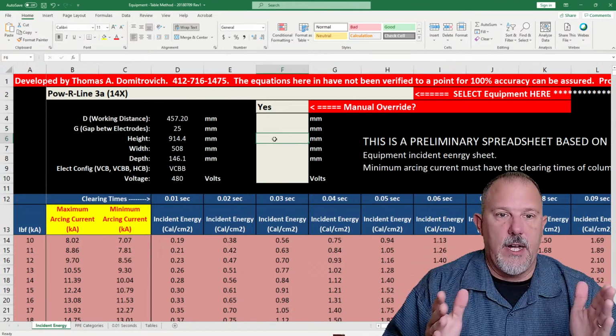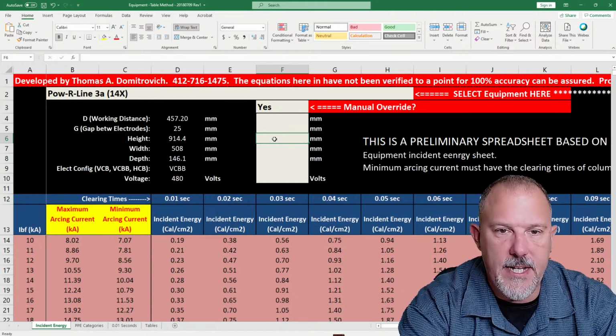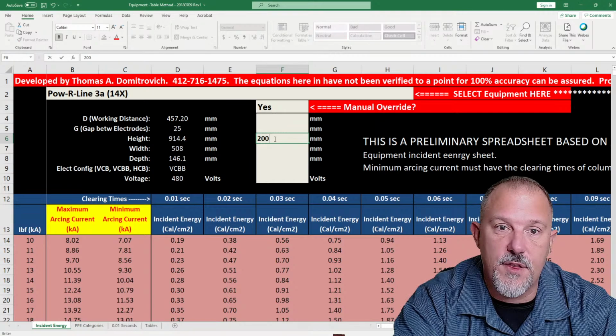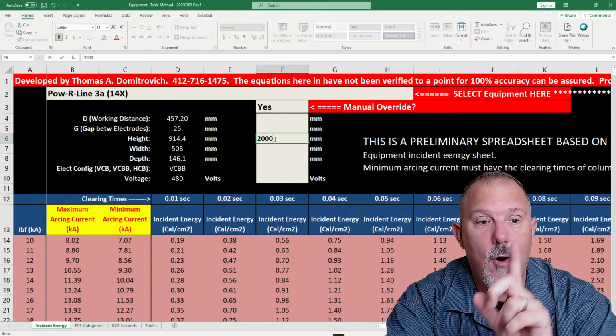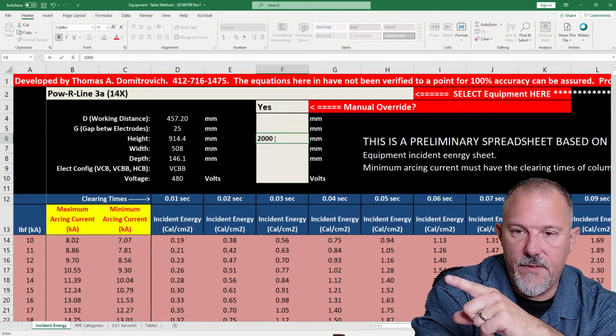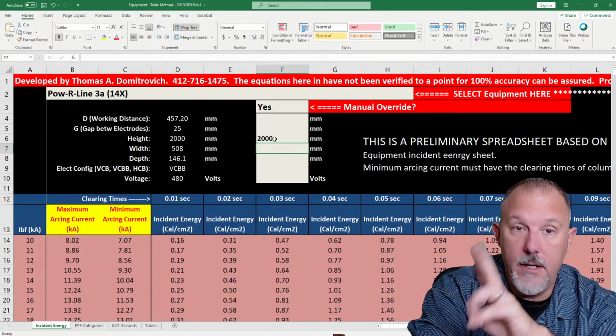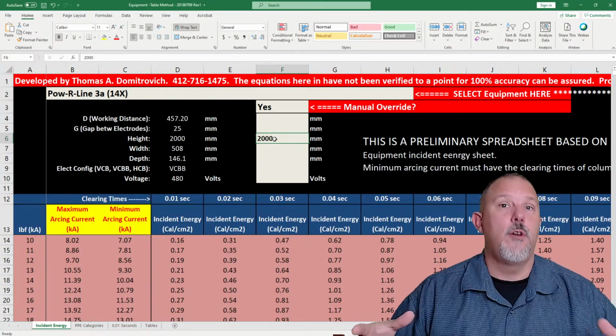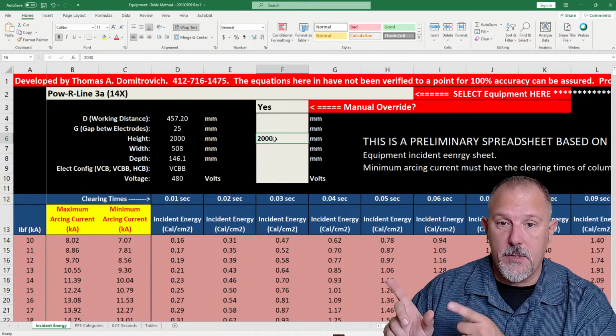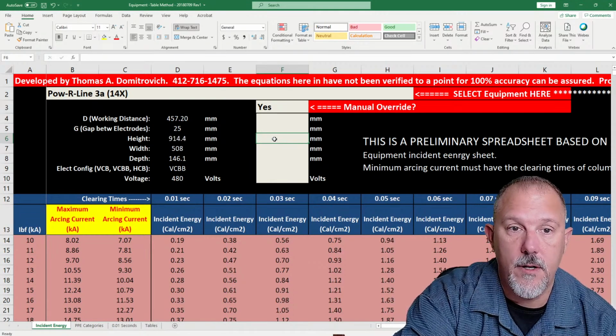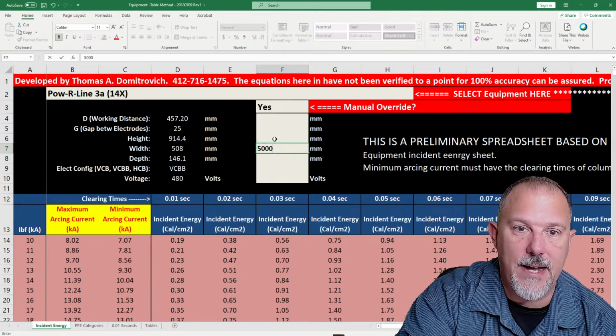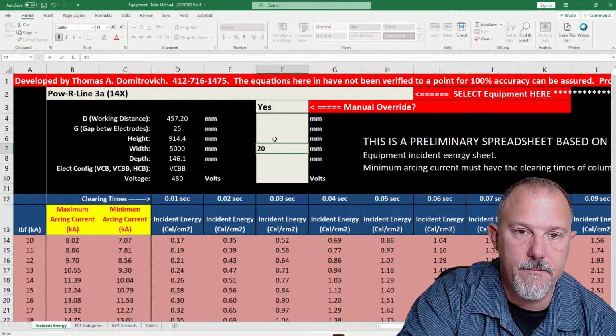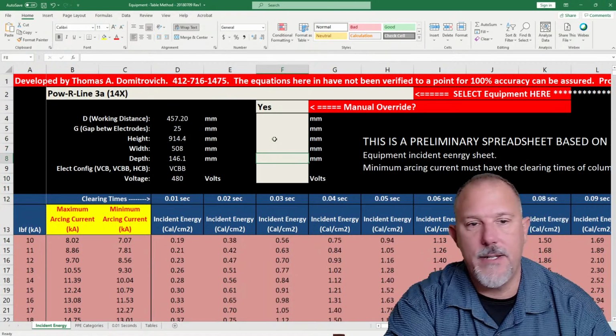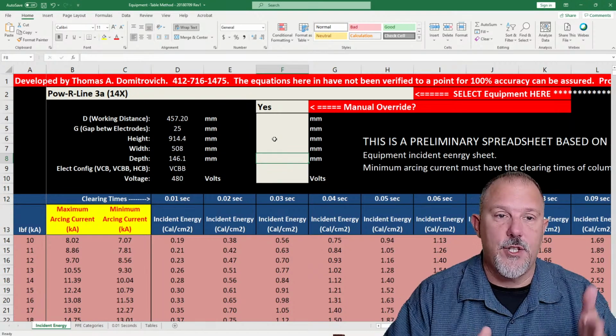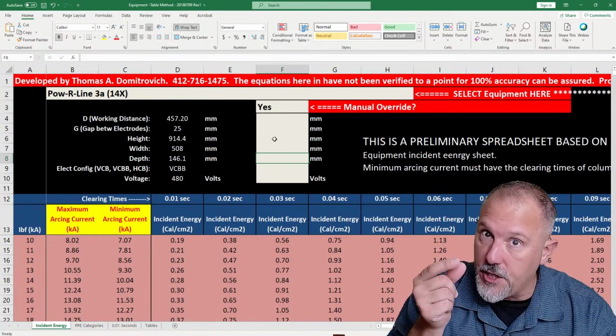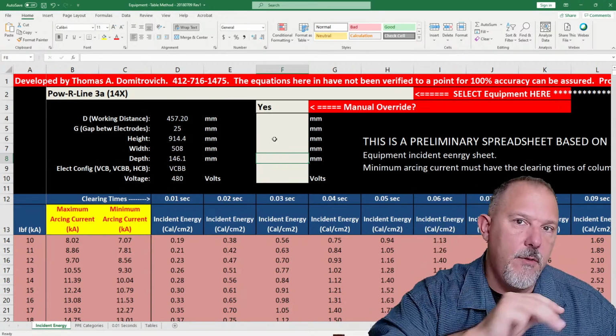How about the enclosure size, the height, width, and depth? 914 millimeters. Let's say I take the height up to 2,000 millimeters. When I hit enter, watch the values of arcing current and watch the incident energy. Arcing current did not change. So the size of my enclosure does not play a role in arcing current, but it does play a role in incident energy. I can take the width up to 5,000, or I could take the width down to 20. And depth, in fact, if you even look at the equations, only plays a role when it's really, really shallow, so I'm not even going to play with that. So height, width, and depth do not impact arcing current.